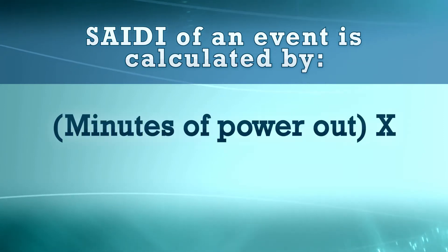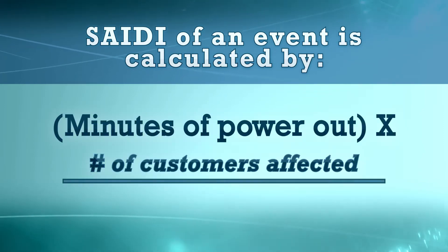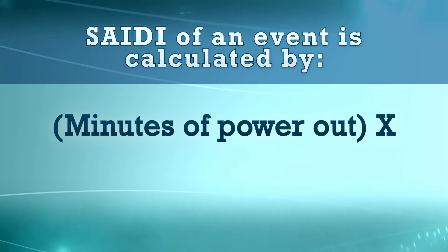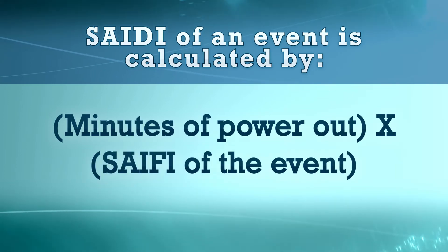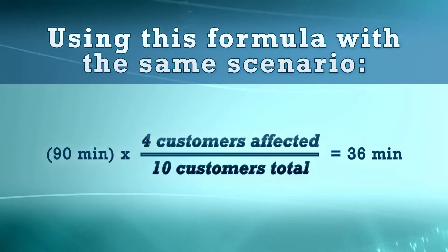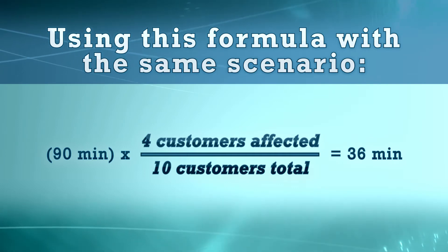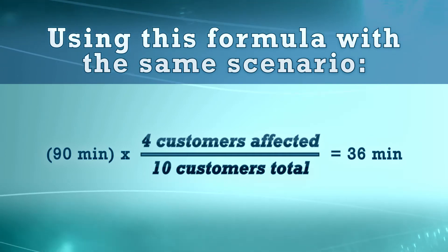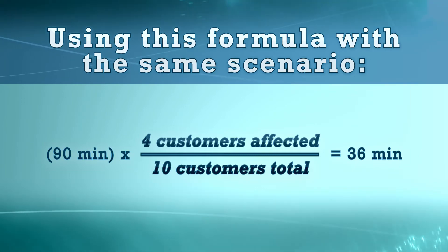SAIDI of an event is calculated by the minutes of power out times the number of customers affected, divided by the number of customers in the system. It can also be described by the minutes of power out times the SAIFI of an event. Using this formula with the same scenario, we have 90 minutes times four customers affected divided by ten customers total, equals 36 minutes, or 36 SAIDI minutes for the event.